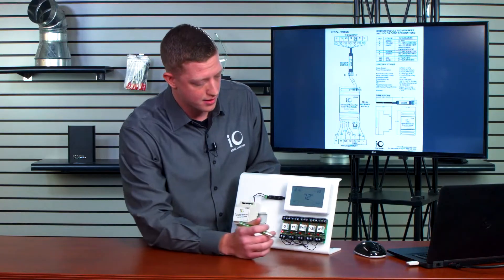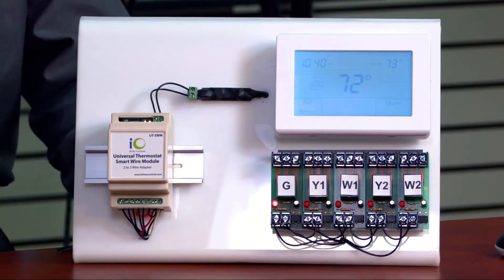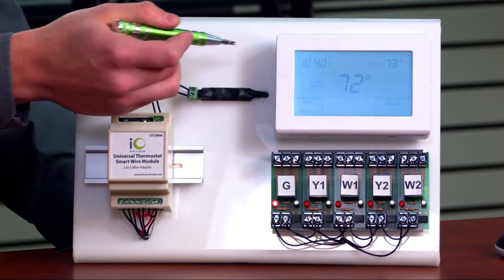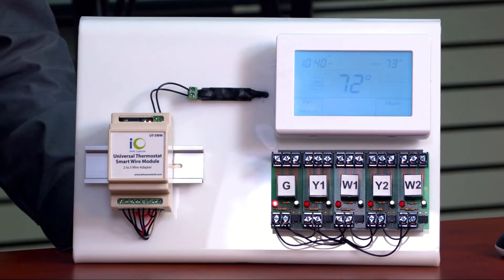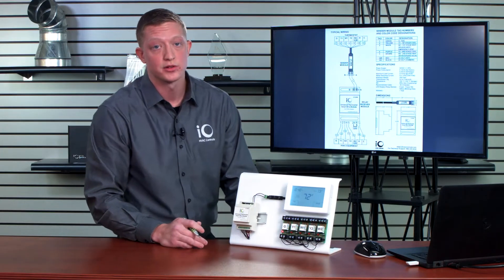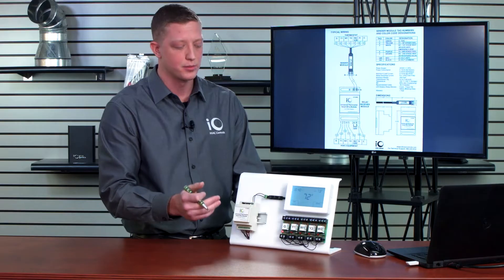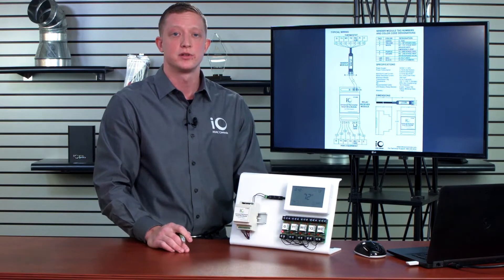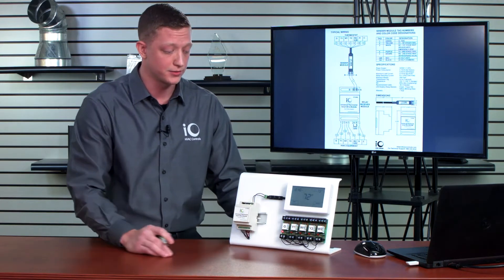Now I'm going to go ahead and get a heating call going on. My thermostat is now calling for first stage heating, and that 24-volt signal is coming from my thermostat to the sending module, and then my receiving module is interpreting that information. Once my receiving module has picked up that information, it's going to send the signal to the appropriate location, so W1 should illuminate as my receiving module has sent the call on to the furnace.